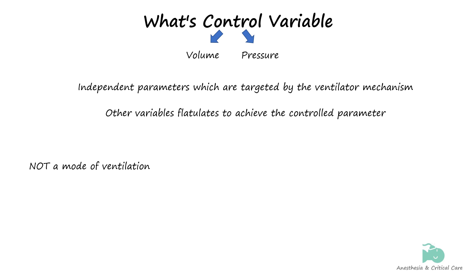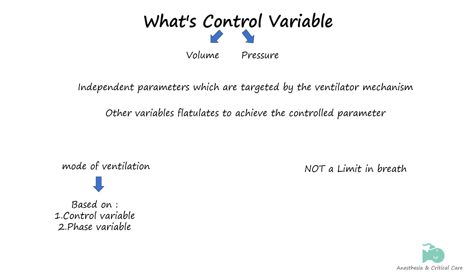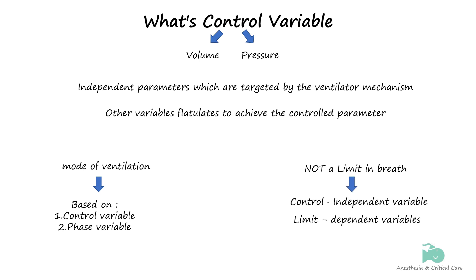The ventilator mode is determined by the characteristics or settings of control variables and phase variables. Another thing to distinguish is that the control variable is not the same as the limit variable of the inspiratory phase. While the control variable exclusively controls or limits one parameter of interest, limits are set to make sure all the other dependent variables don't go out of control in the process of achieving the control variable.